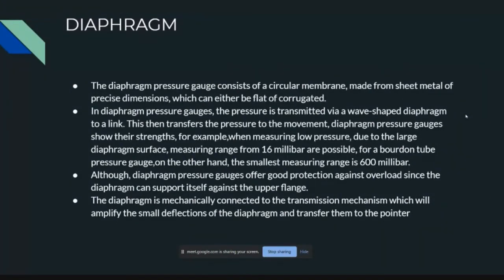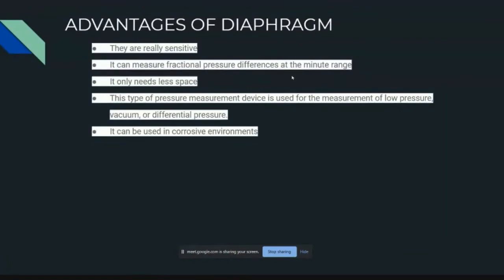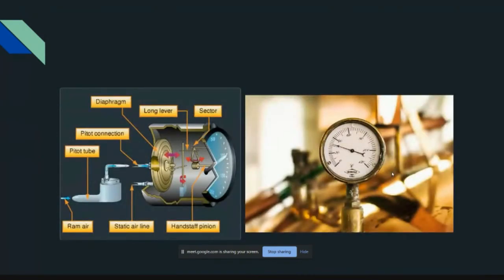Next, about the diaphragm. Here are some of the advantages of the diaphragm. We can see they are really sensitive. It can measure fractional pressure differences in the minute range. It only needs less space. This type of pressure measurement device is used for the measurement of low pressure, vacuum or differential pressure. It can be used in corrosive environments. Here is the diagram of the diaphragm. There are some parts: diaphragm, long lever, sector, Pitot connection, Pitot tube, ram air, static airline, handstaff pinion.